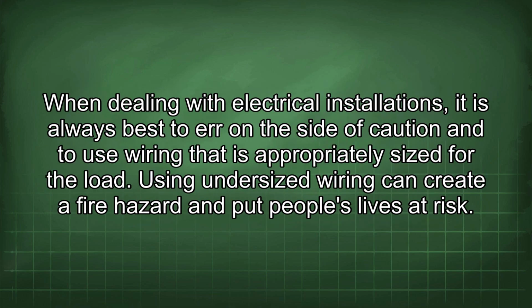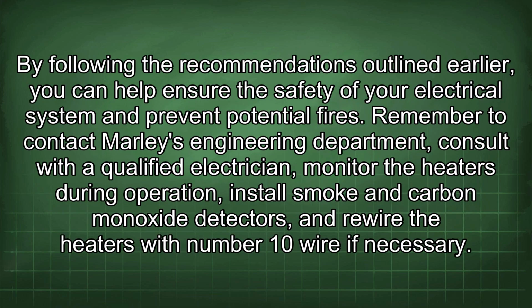When dealing with electrical installations, it is always best to err on the side of caution and to use wiring that is appropriately sized for the load. Using undersized wiring can create a fire hazard and put people's lives at risk. By following the recommendations outlined earlier, you can help ensure the safety of your electrical system and prevent potential fires. Remember to contact Marley's engineering department, consult with a qualified electrician, monitor the heaters during operation, install smoke and carbon monoxide detectors, and rewire the heaters with number 10 wire if necessary.